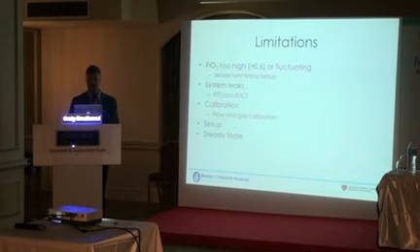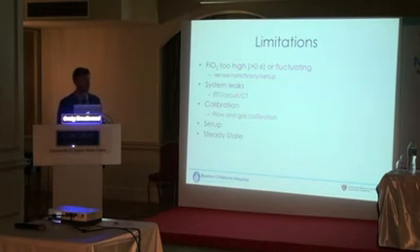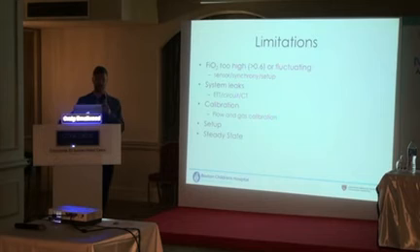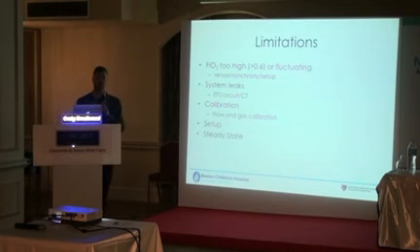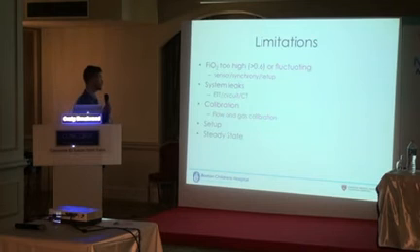So some limitations. Then I have a couple of studies from my lab just looking at some comparisons in terms of accuracy in pediatric and neonatal children. A lot of devices won't measure accurately at high concentrations of oxygen. Some of them do, but you want to make sure that if you apply these devices, you're using them within the manufacturer's specifications. They're going to be sensitive to system leaks.